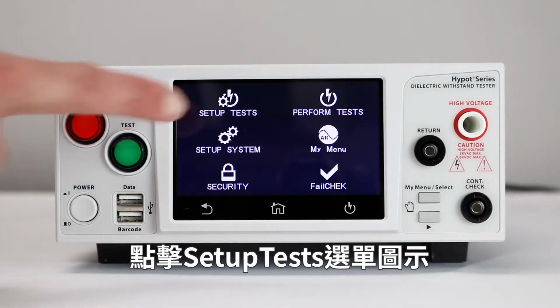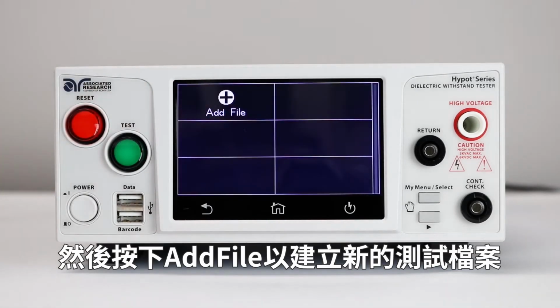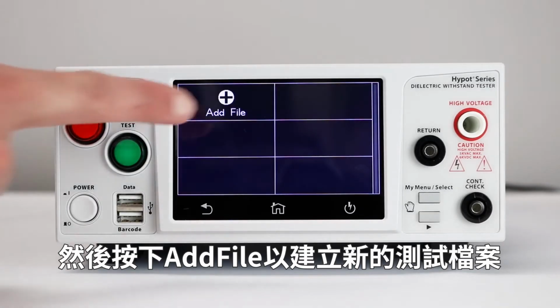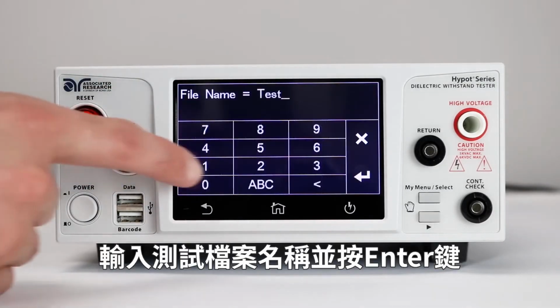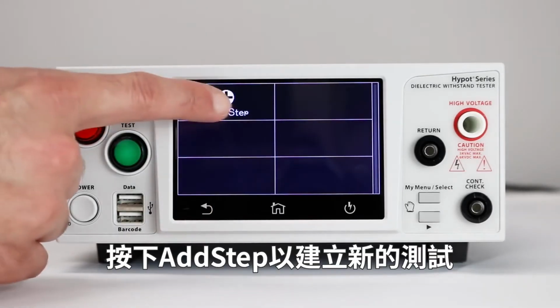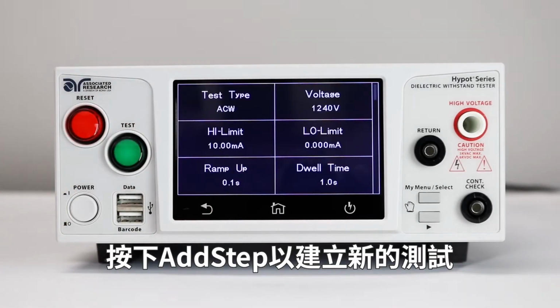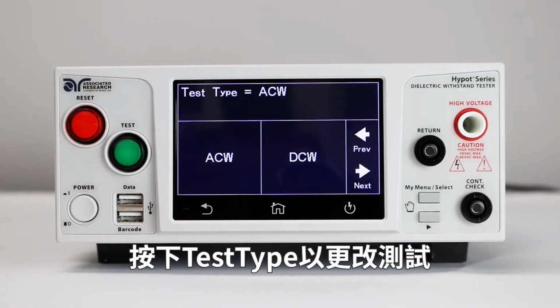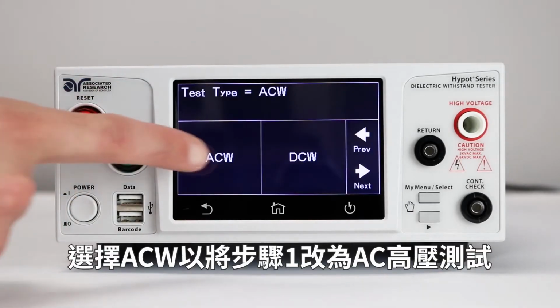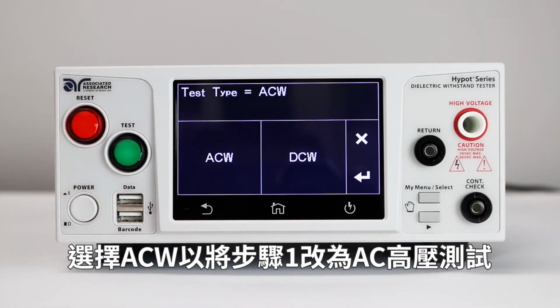Touch the Setup Test menu icon, then press Add File to create a new test file. Input the test file name and hit Enter. Press Add Step to create a new test. Press Test Type to change the test. Select ACW to change Step 1 to an AC Hypot test.